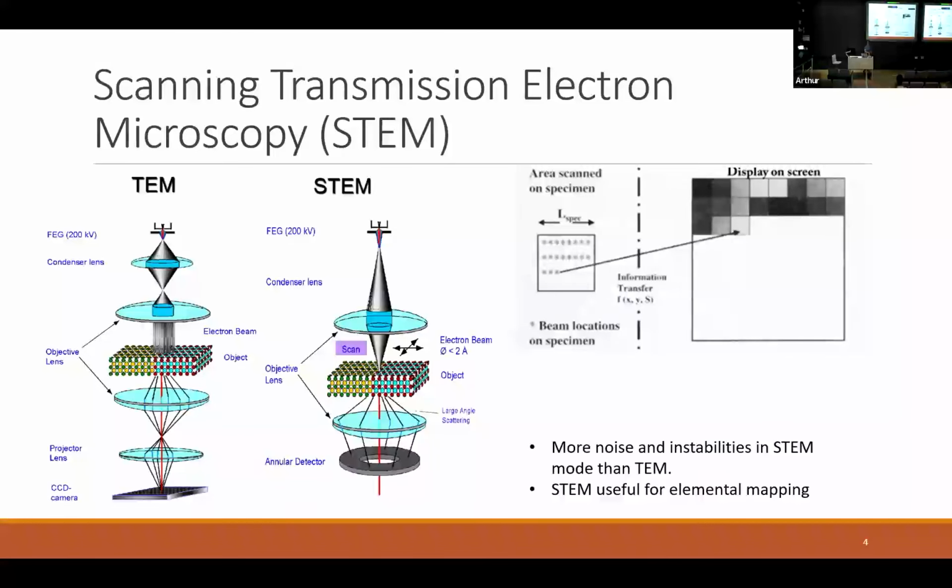There are two main types of transmission electron microscopy. There's standard TEM, and that's what we start all our new users off on. In TEM, which is the diagram on the left here, you have a broad beam of electrons hitting your sample and passing through it. That interferes with the sample and generates an image, and we can project that image plane onto the camera at the bottom of the microscope. The electron beam starts at the gun here, works its way through, here's your sample, and then ends up on the CCD as an image. This is nice. It's less beam sensitive in general, and we're able to get images out of the system really quickly.